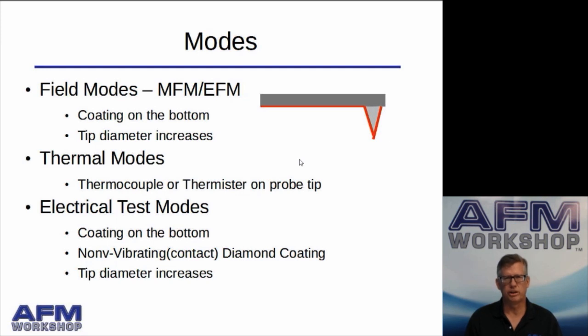Many people like to do field modes with their atomic force microscopes, for example MFM and EFM. In these types of measurements, a coating is put on the bottom of the cantilever, and the coating could be some magnetic coating or some conductive coating. But what's important to remember is that the coating is put on with vapor deposition, so the diameter of the probe increases. If you start out with a probe that has a diameter of, say, 30 nanometers, and you put a 50 nanometer coating on it, the diameter of the probe gets much larger. So for a lot of these field modes, the ultimate resolutions are not as good as they would be with a standard topography measurement with an AFM.